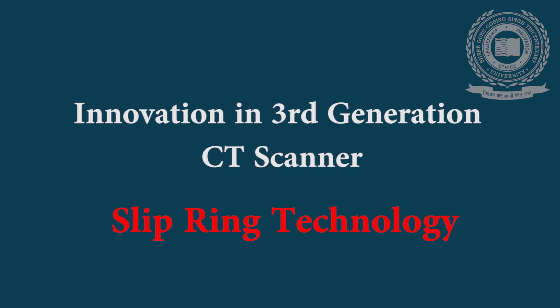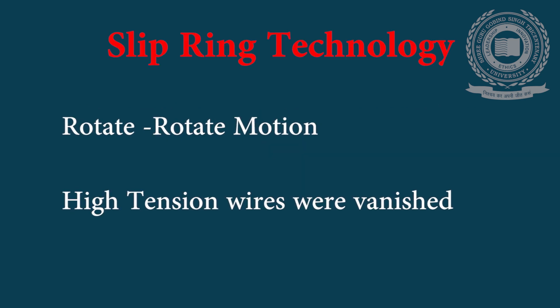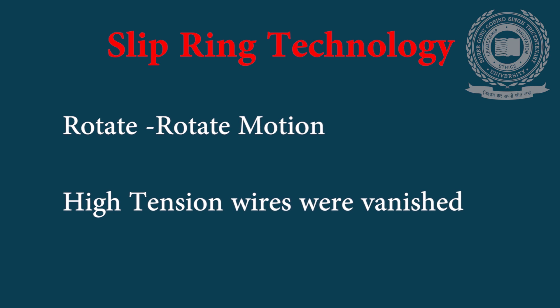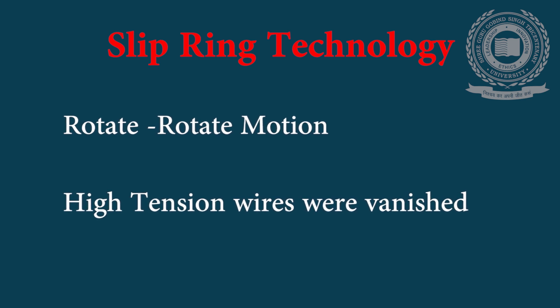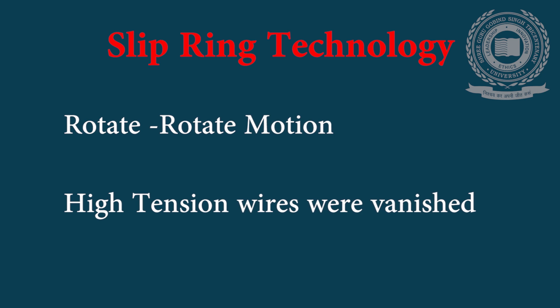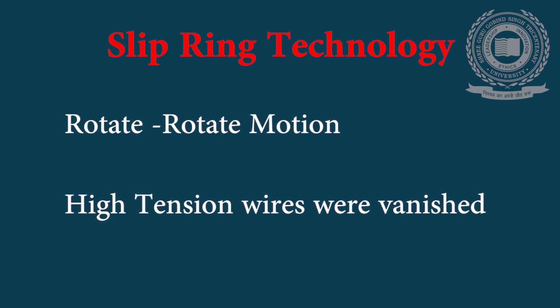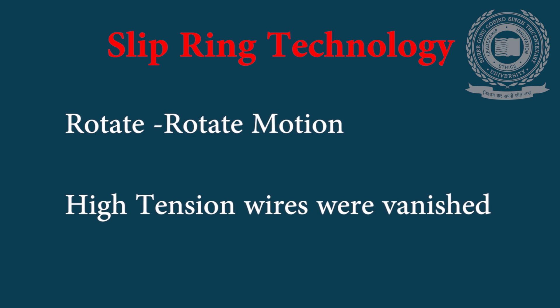And very soon one innovation was done by scientists, that was slip ring technology. Slip ring technology was the biggest advancement in the third generation which changed the complete era of scanner. Due to slip ring technology, rotate-rotate motions of X-ray tube and detector is happening without any loop of high tension wires. Physics behind this slip ring technology will be discussed in the instrumentation chapter.